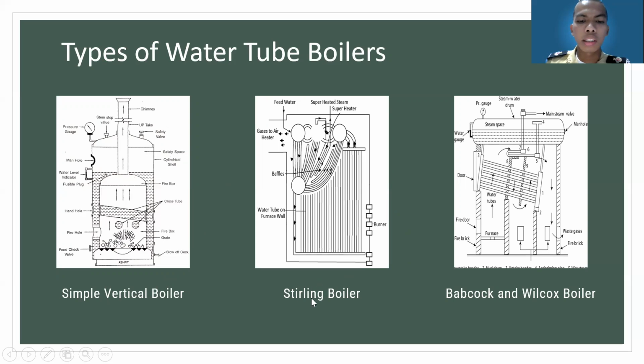And number two is the Stirling boiler. The Stirling boiler is a bent tube, externally fired, stationary water tube boiler with natural circulation. It has a maximum pressure range of 60 bar and a steam production of about 50,000 kilograms per hour. The efficiency of the Stirling boiler is up to 60% to 80%.